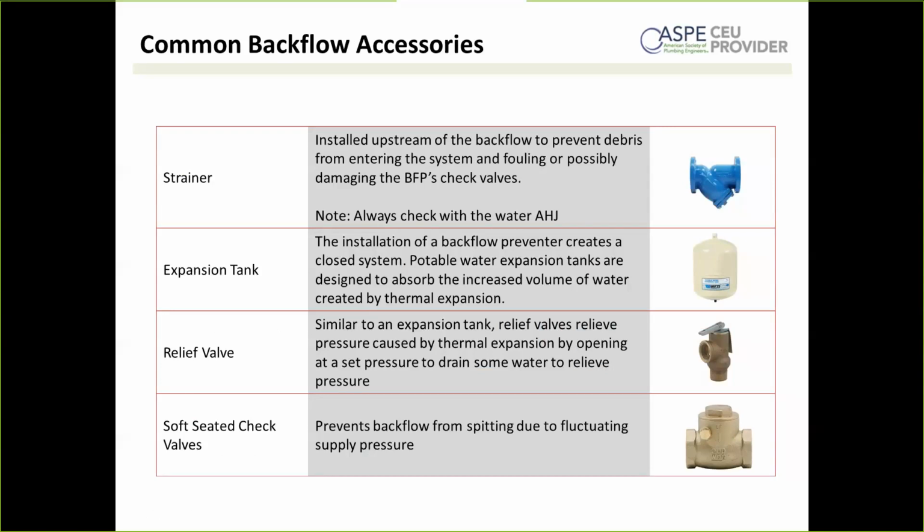That means if you have some thermal expansion, it doesn't have as much volume to go ahead and absorb that. So you can get dramatically increased pressures, which can start doing things like breaking second checks, which will cause some significant discharge.